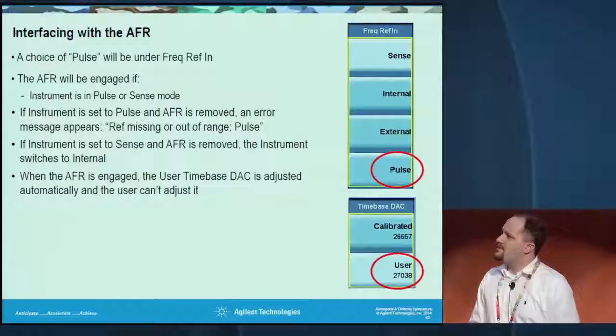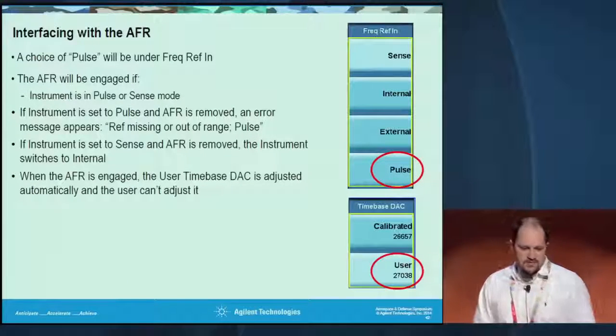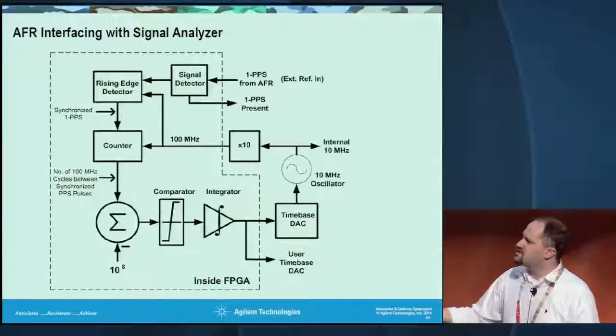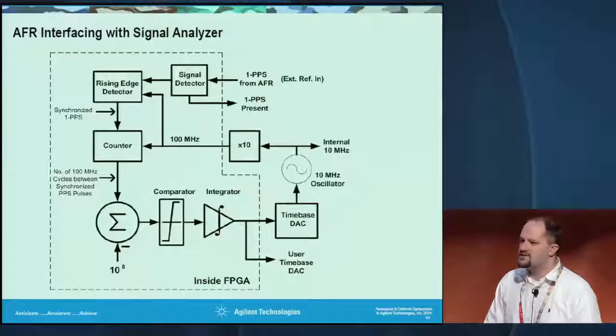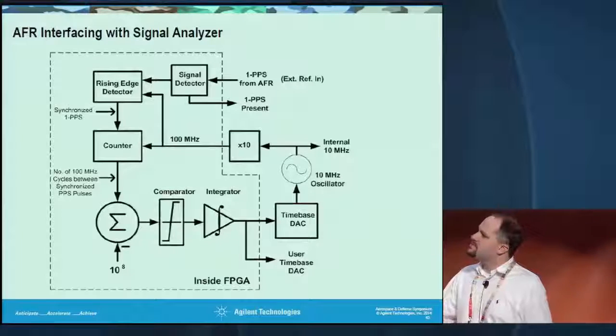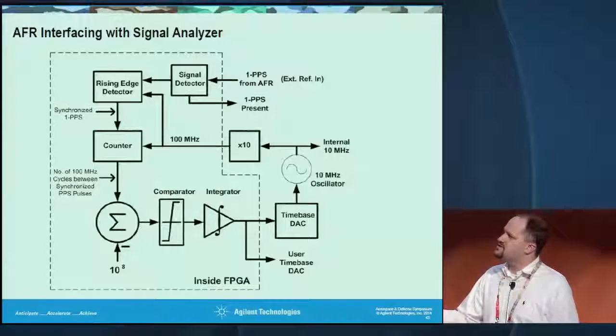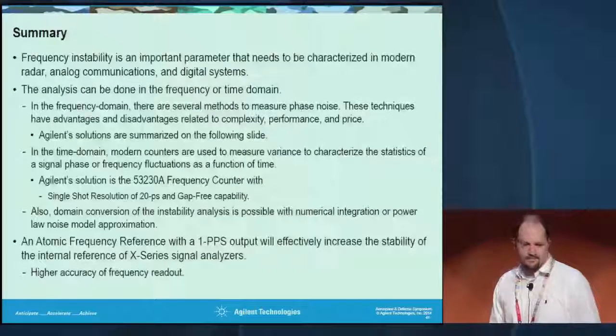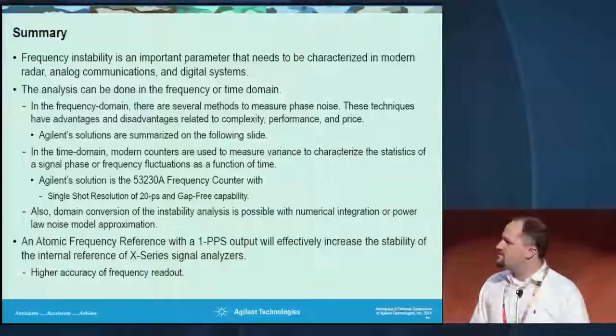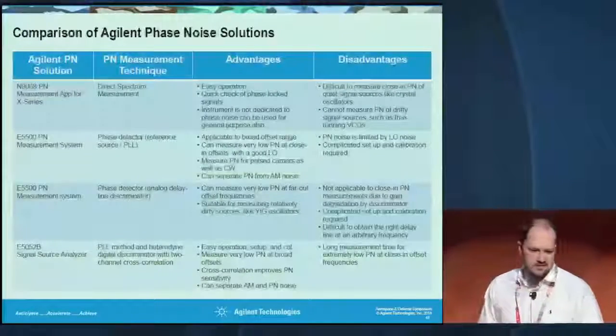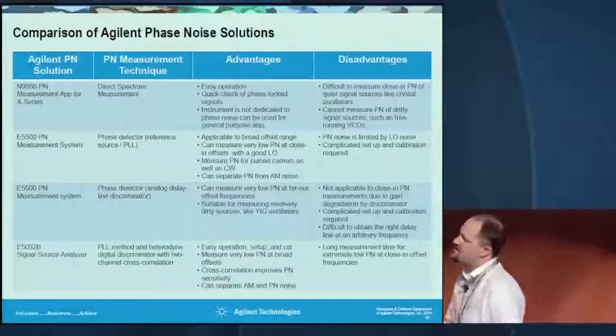Last but not least, interfacing with a new atomic frequency reference for long-term stability. What we do is train the FPGA inside the signal analyzer by detecting a one pulse-per-second signal based on a cesium standard, which is very repeatable. We compare that and adjust our time base over time. That's the summary — thank you very much.